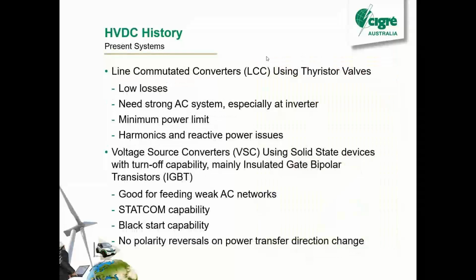So the present systems that are available for HVDC, you can still buy the line commutated converters. They've been around for a long time, but the main benefit we still have with the LCC is the low losses. After that, it's pretty much all negatives. You need to have a strong AC system, especially at the inverter with LCC. LCC also has a minimum power limit, and it has harmonic and reactive power issues, which we'll go into in more detail later.